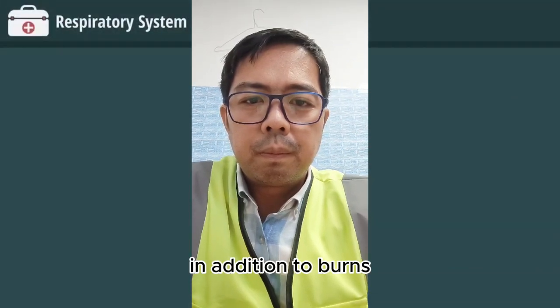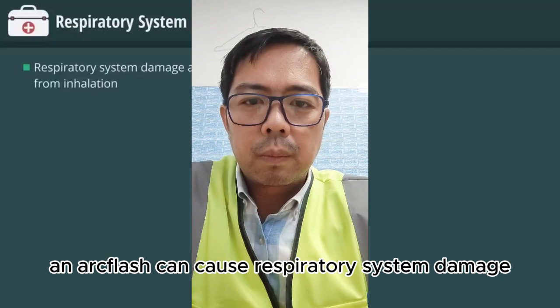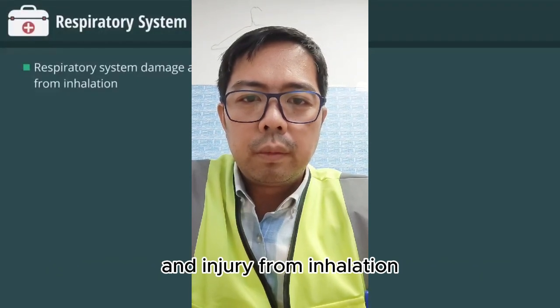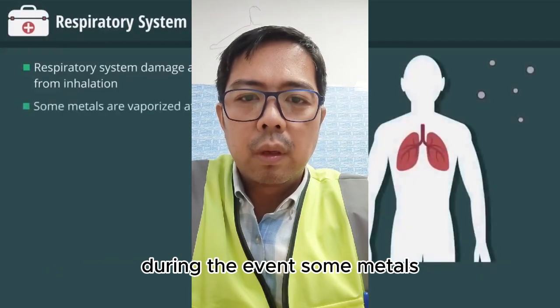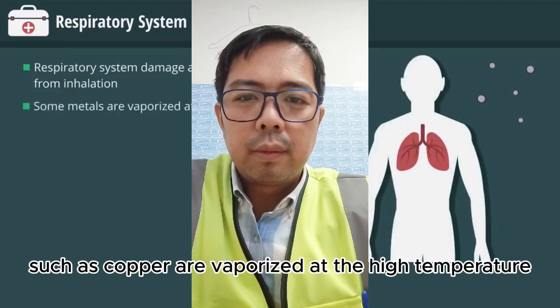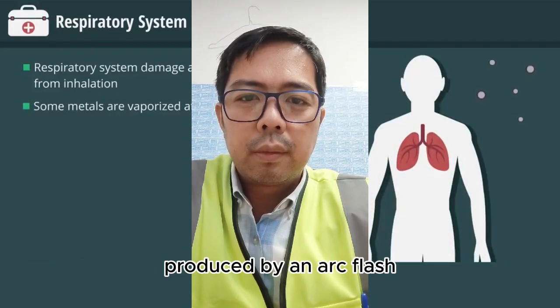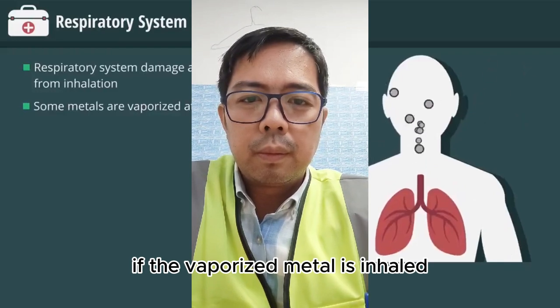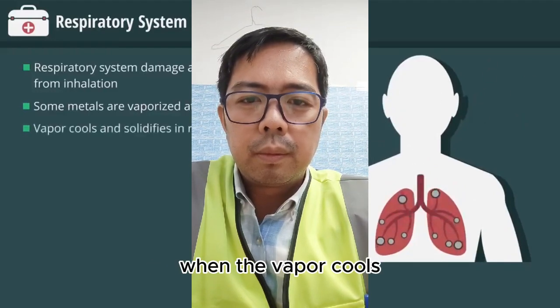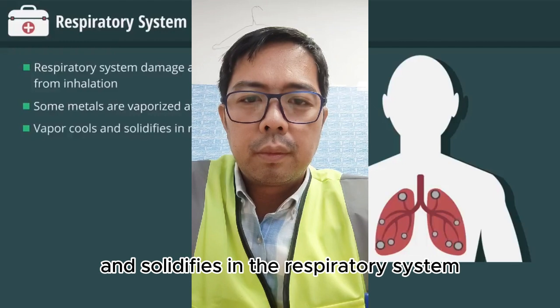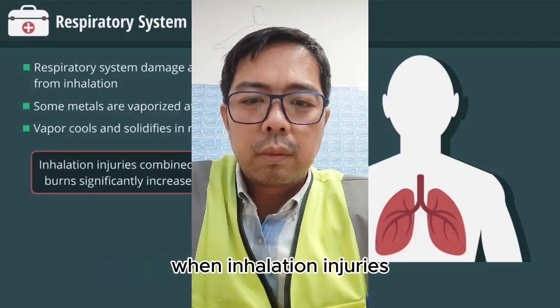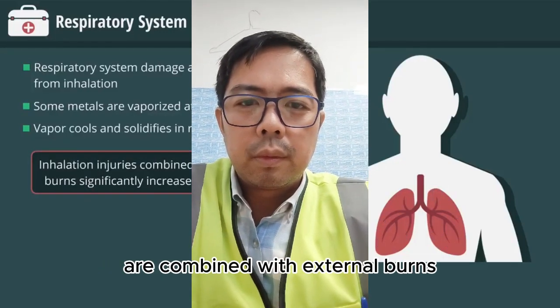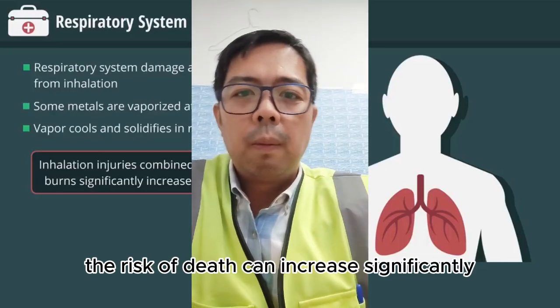In addition to burns, an arc flash can cause respiratory system damage and injury from inhalation during the event. Some metals, such as copper, are vaporized at the high temperature produced by an arc flash. If the vaporized metal is inhaled, serious lung damage occurs when the vapor cools and solidifies in the respiratory system. When inhalation injuries are combined with external burns, the risk of death can increase significantly.